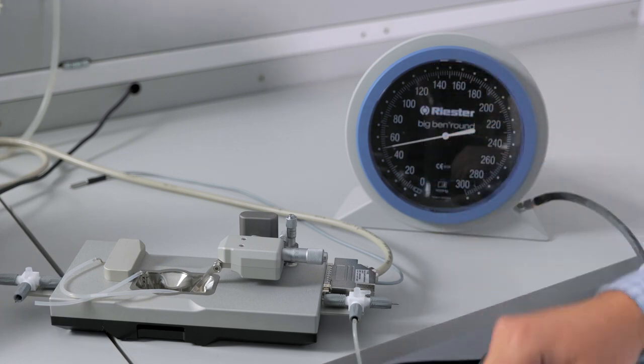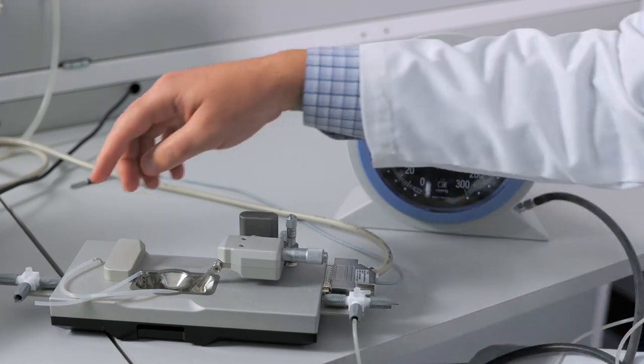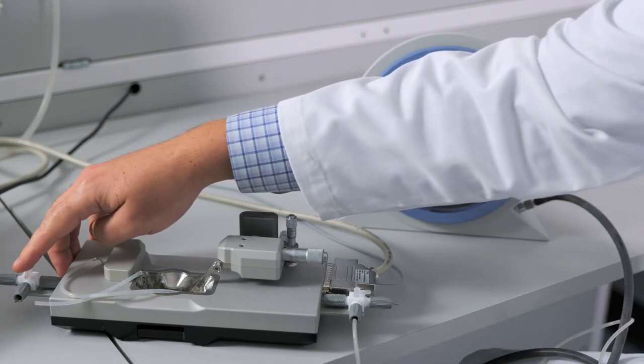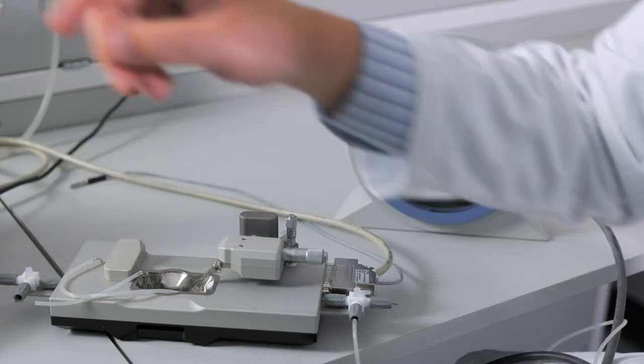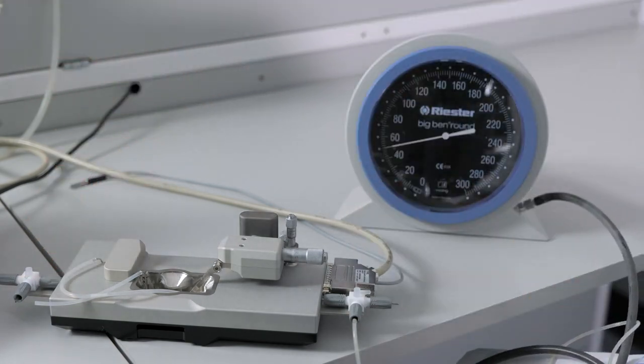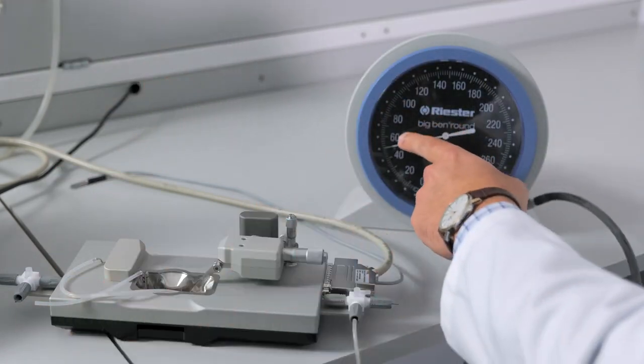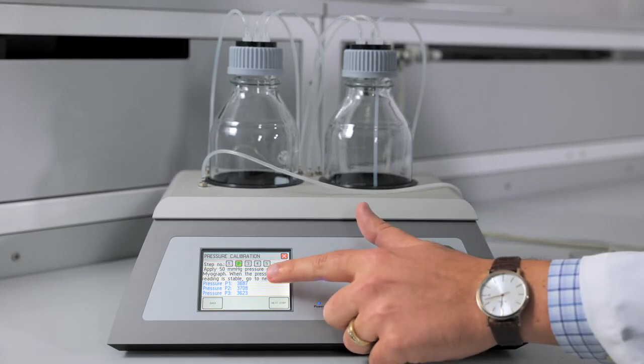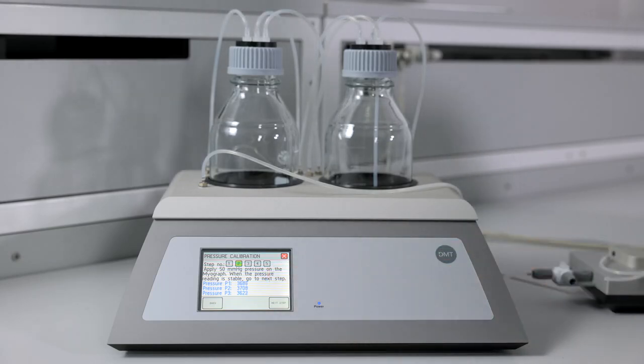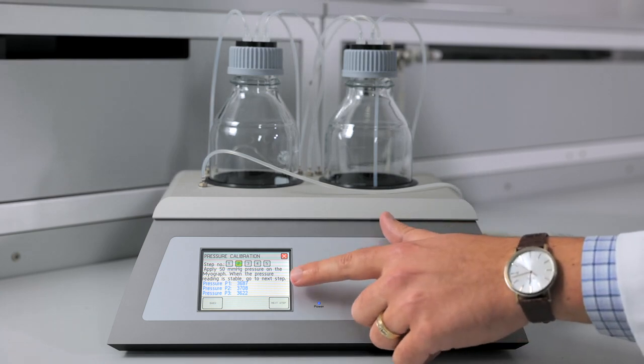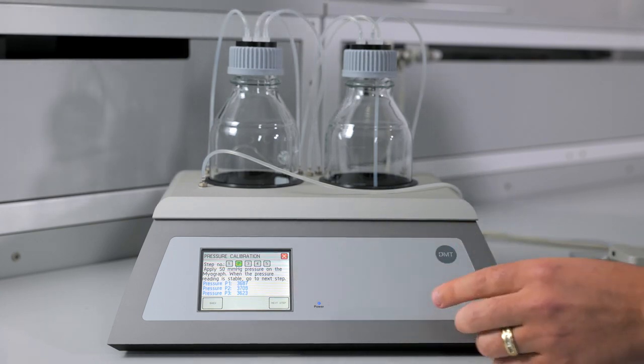If you are losing pressure, that means you have a leak somewhere. It could mean that you have the three-way valve in the wrong direction, your bottle cap not tightened, or a leak in the tubing. But the pressure is holding at 50, and you can see the P1, P2, and P3 pressure readings have all increased. At each step, you want to make sure that the readings are increasing similarly. So these are all in the 3600 to 3700 range, which is good.